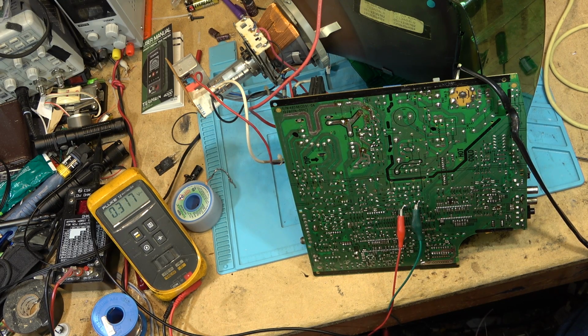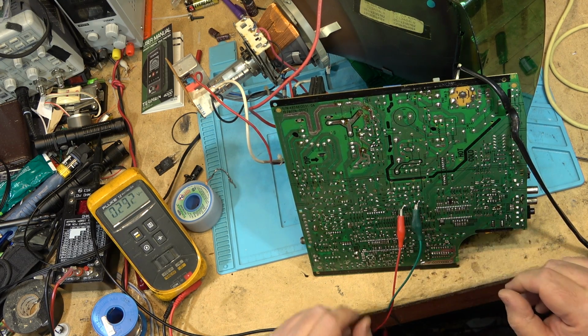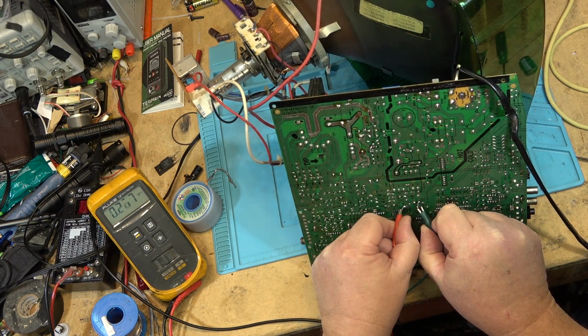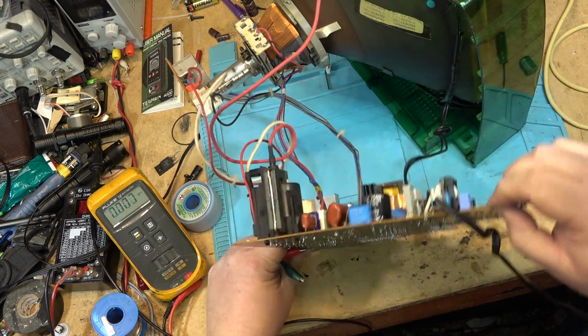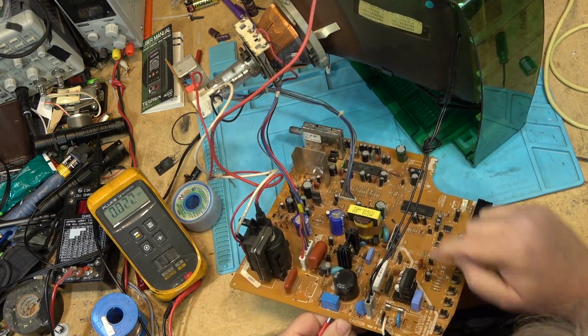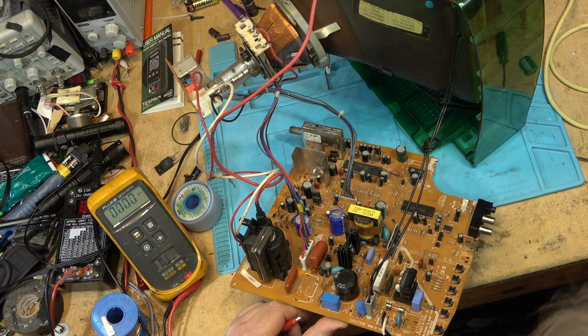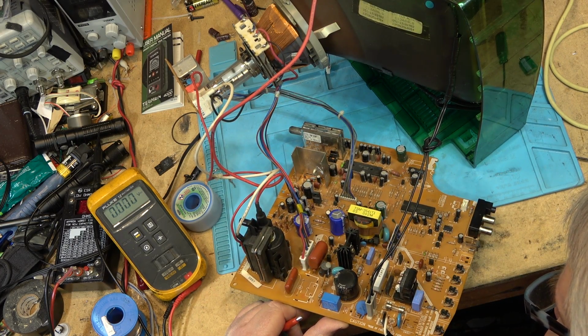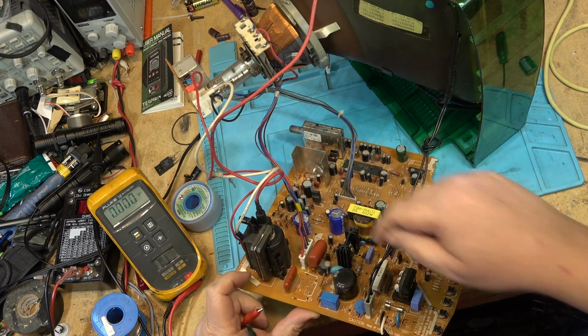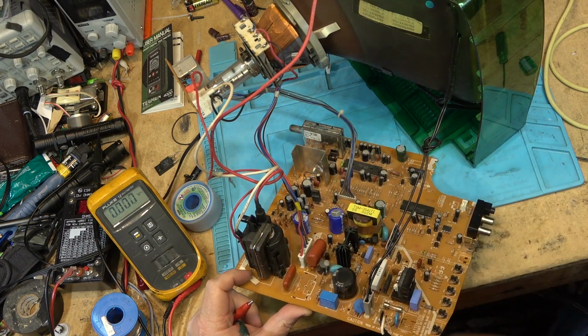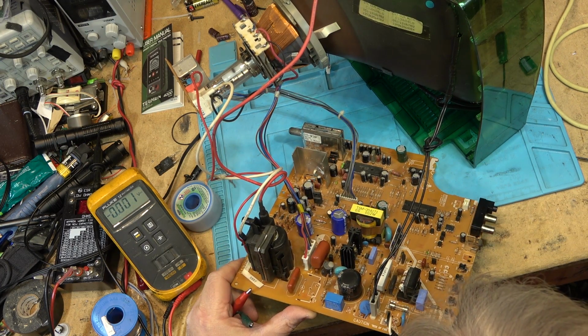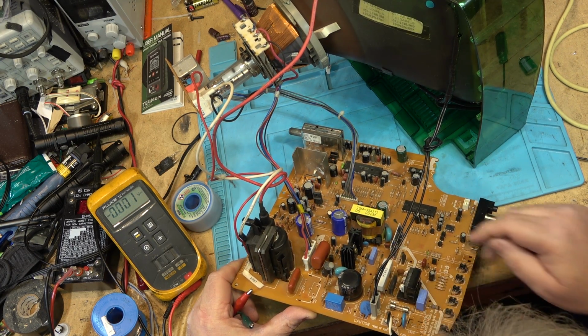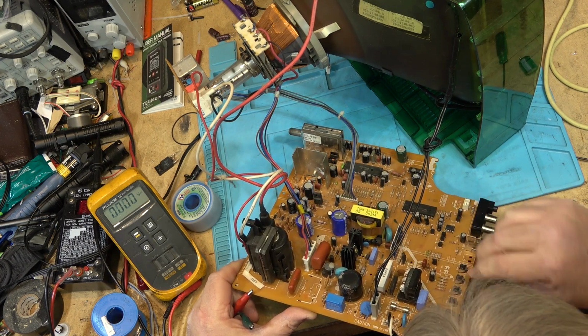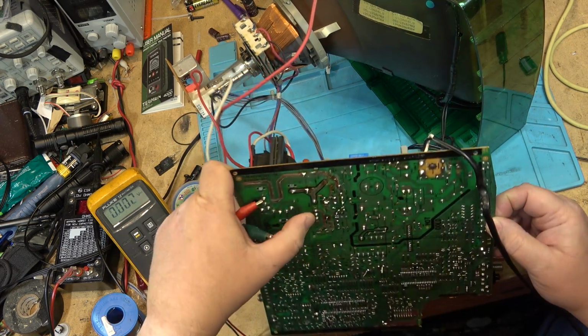So I get a sneaking suspicion it's this regulator right here that is at fault — this hybrid part, on the ceramic board. It's got the optocouplers and everything on it, and the voltage regulator, and that's where I think our problem is that failed. That caused the voltage to go too high, which ultimately blew the crowbar and shut the set down. So we're gonna have to try to source that part, because I'm sure that's probably where the fault is on this.